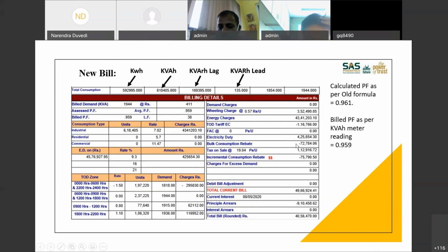This 5,92,995 is the total consumption. Rather, 618,405 is the basic consumption. They will reduce 1 lakh from this, and for the rest of the 5 lakh you have to calculate the energy charges based on 7 rupees 2 paisa, and 2% of that will come here as bulk consumption discount. They have also calculated an incremental consumption rebate here, because this consumer must have consumed more than his average of last year in this month. This particular industry was a small pharmaceutical industry in Mahad, so they were never closed. They had no shutdowns due to COVID, being in essential services, and because of that, their bill is almost the same as what it was in normal cases.